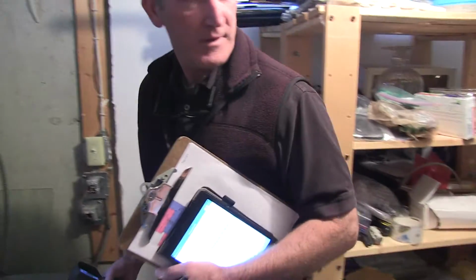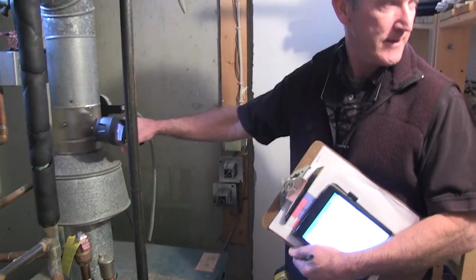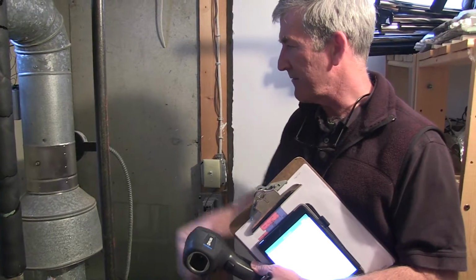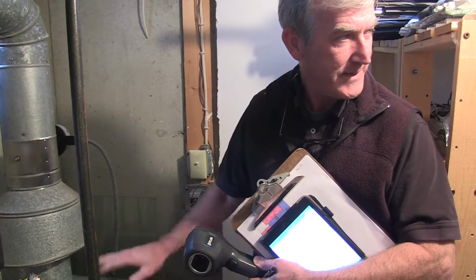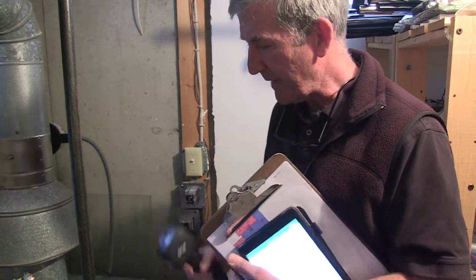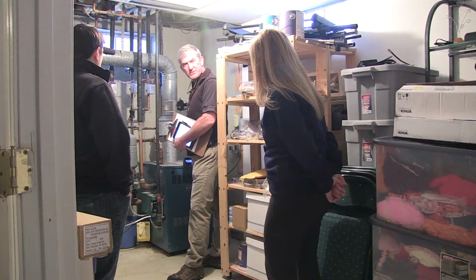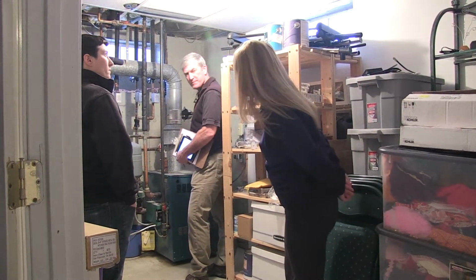So you've got an atmospheric boiler, and you've got a bonnet damper on it with an electrical damper. The way that your system works here is when it's not firing, there's a flap within this system that closes, which allows it to maintain heat because there's a pilot burning within the system. I'm assuming this is the original boiler. It hasn't been updated since you've... That is correct. Certainly appears that way.